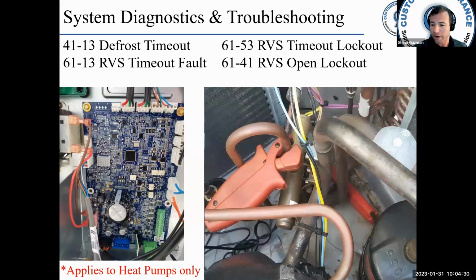Here we can see this is in cooling cycle. So I would read discharge right here. And then the line down there at the bottom is discharge going to my condenser coil, which is over here. I hope you guys are following me there. I did misspeak a few minutes ago. So check your temperature difference, right?